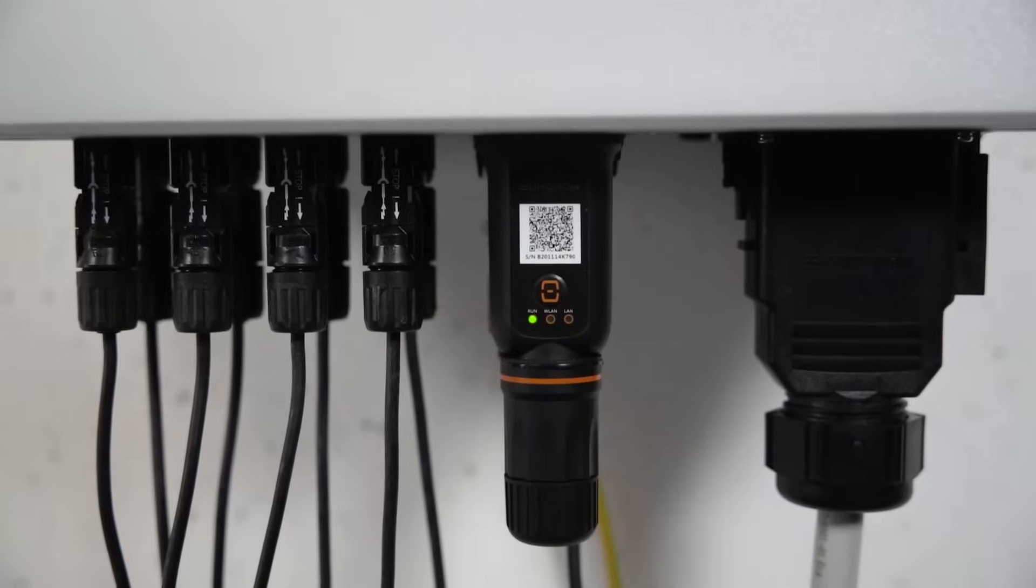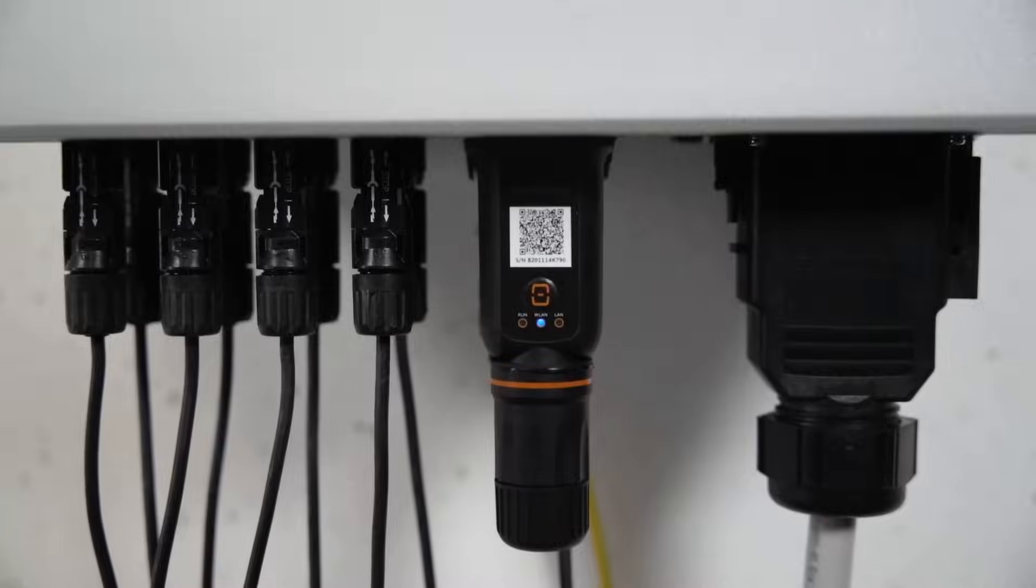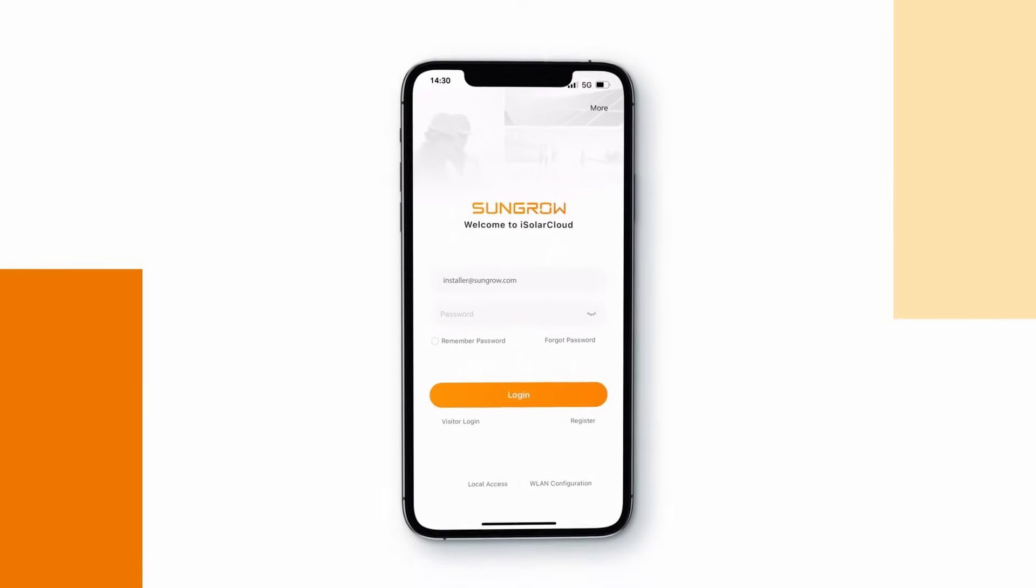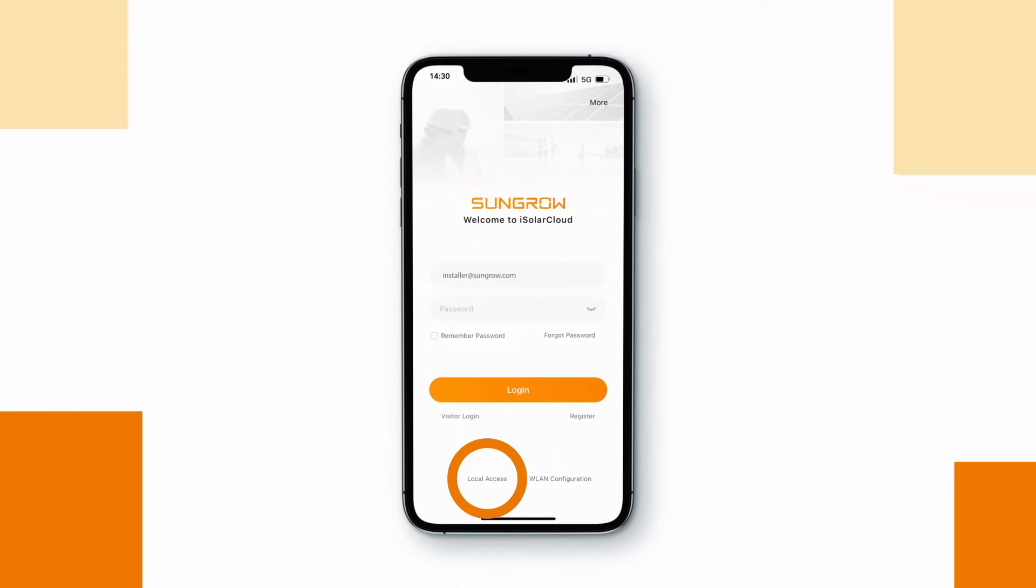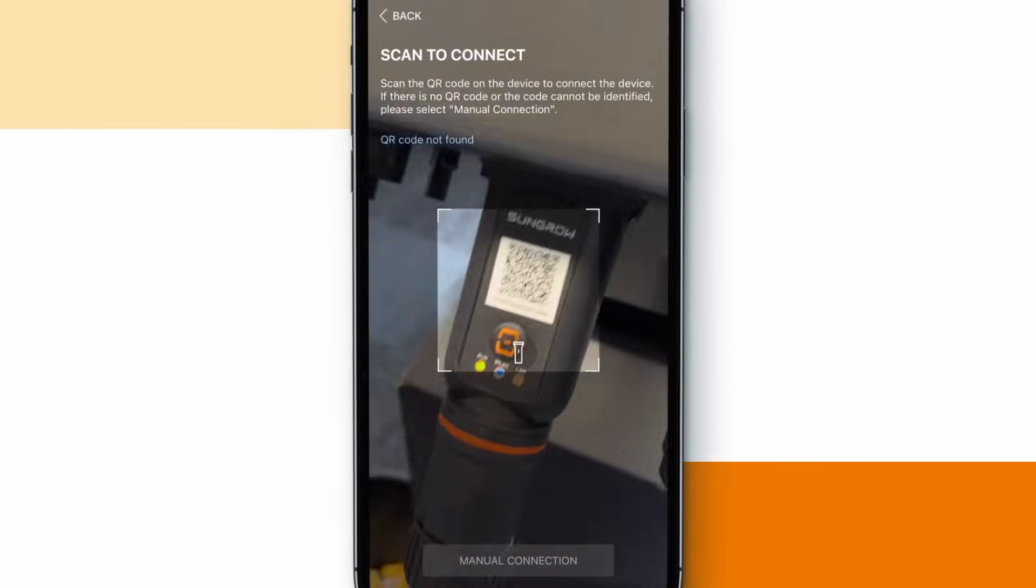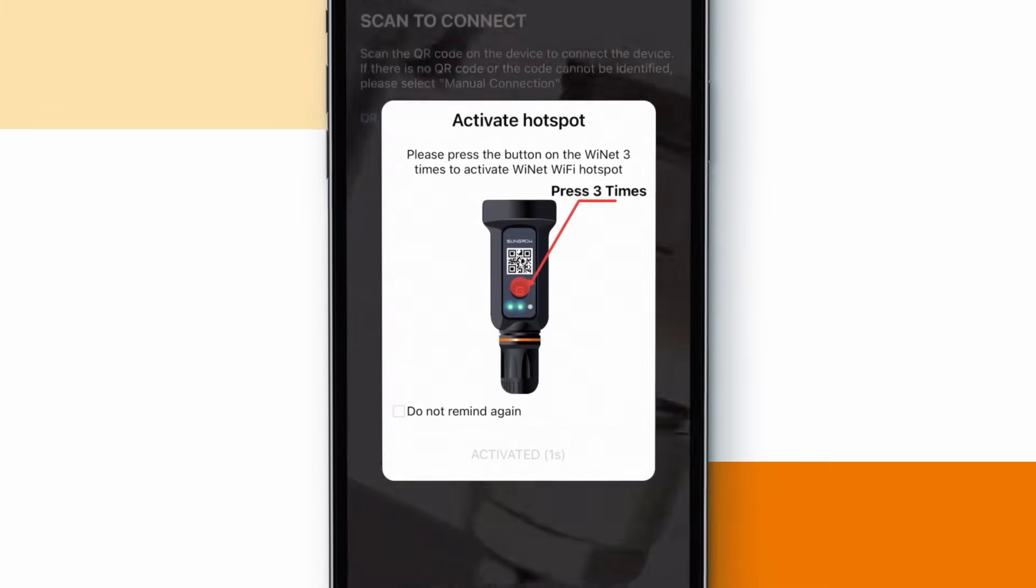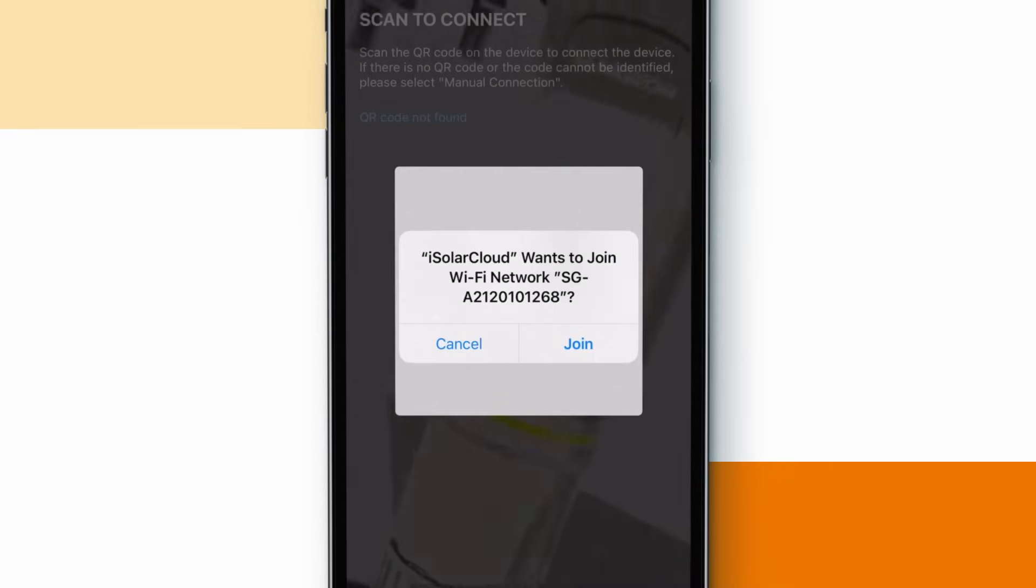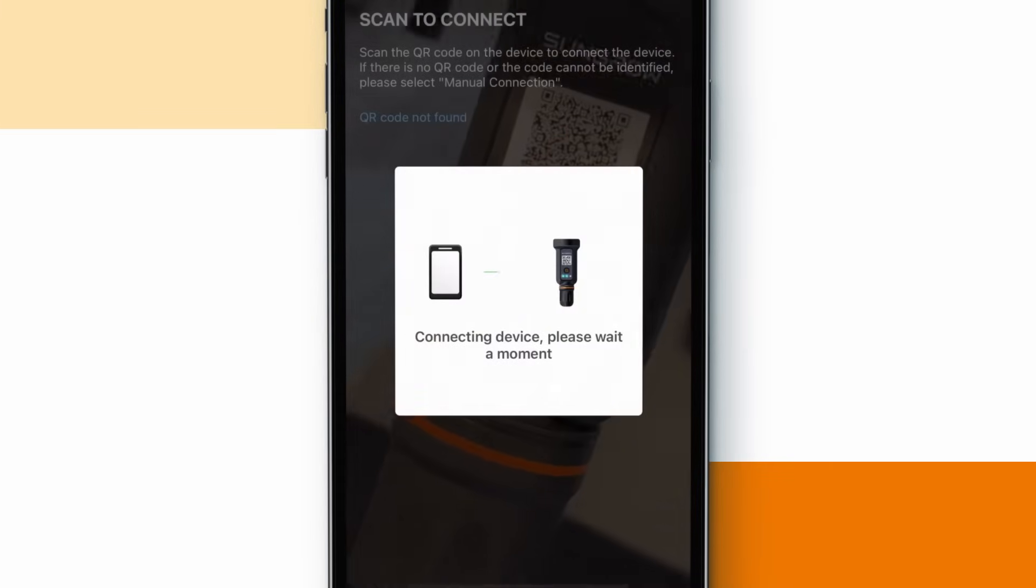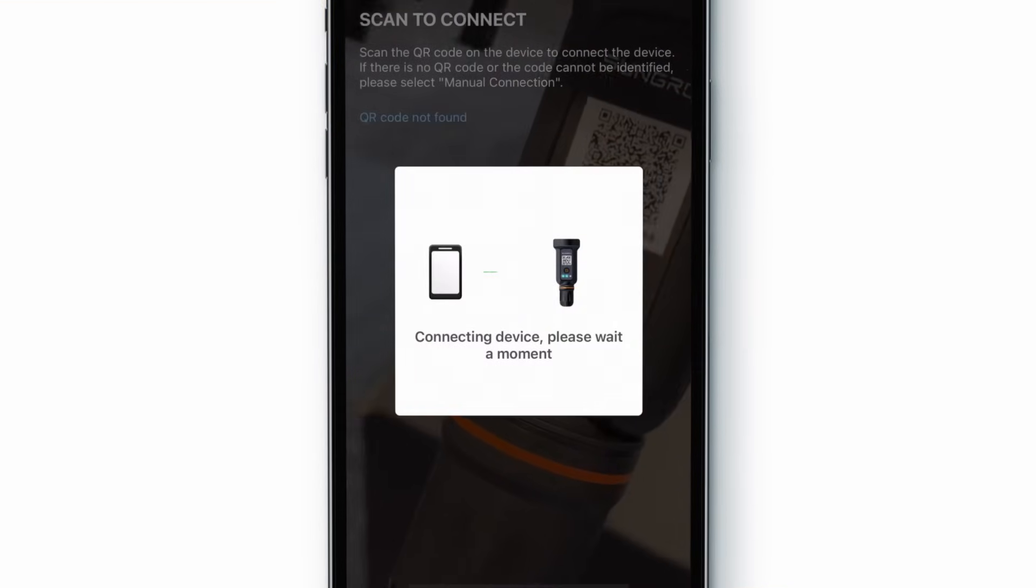So let's start with the on-site commissioning. Open the iSolarCloud app and click on local access at the bottom left. Scan the QR code on the WiNet module. Press the orange button three times. Click join to connect to the WiNet hotspot and to proceed with the device initialization.